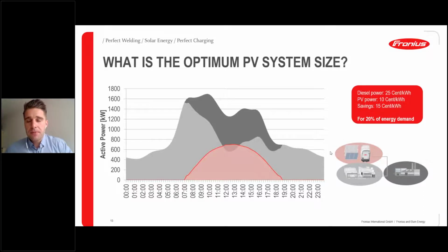And you have these 3 components again, which means the light gray one, that's the genset load, the dark gray one behind, it's the effective load of the company, for example, and the red one is the PV integration. What I want to tell you with this is that in this configuration, the PV system is considerably small compared to the load and the genset. So you see the PV system generation is at no point exceeding the load demand of the household.